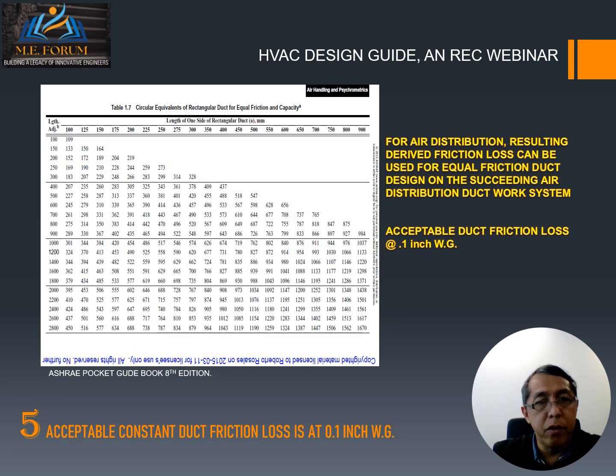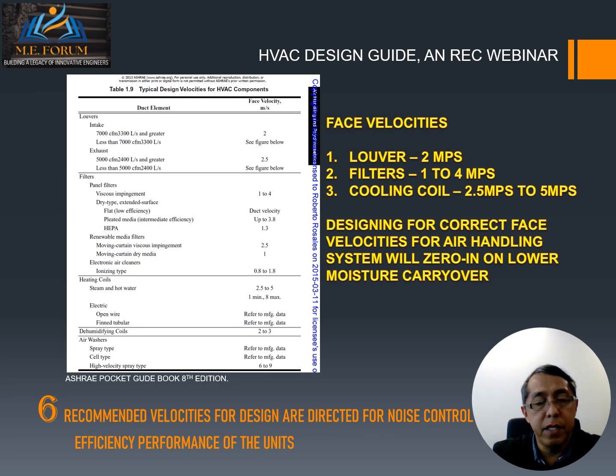Number 5, acceptable constant duct friction loss is at 0.1 inch water gauge. Number 6, recommended velocities for design are directed for noise control and efficiency performance of the units.